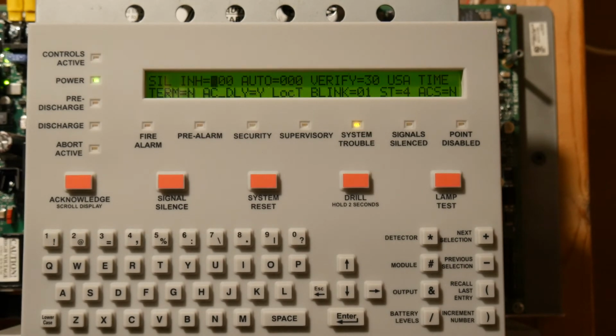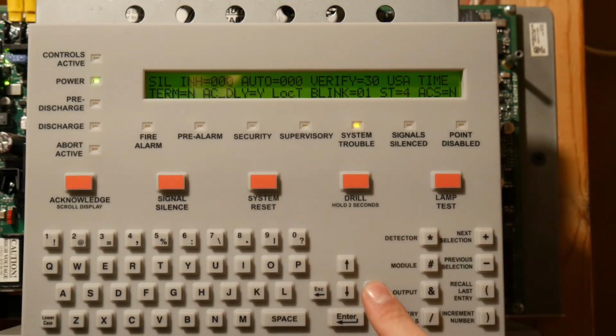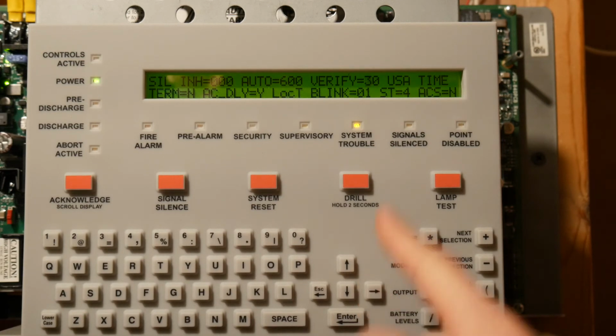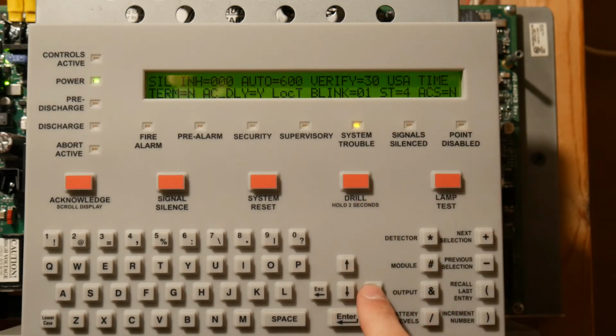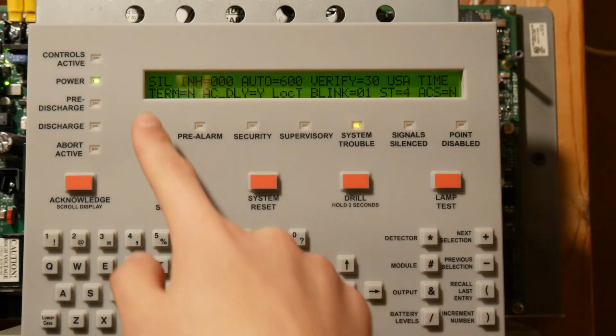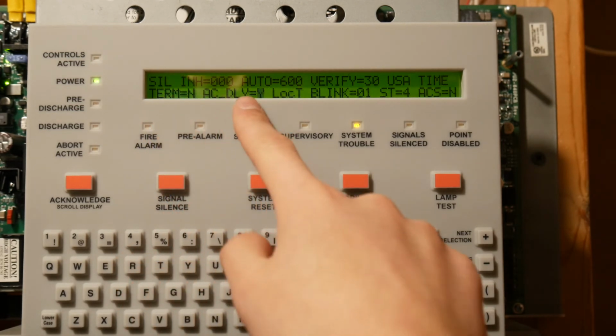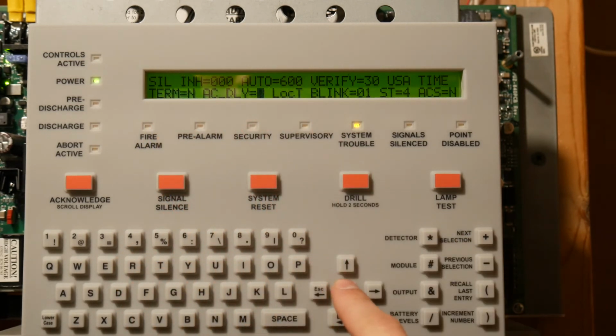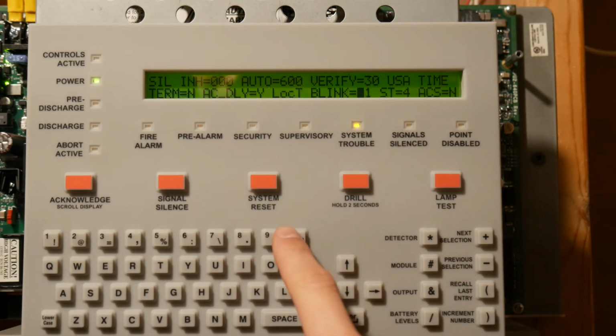Silence inhibit basically means, do you want a certain amount of time to pass before you can press signal silence? I do not want that. Auto silence, yes. I want it to automatically silence after 10 minutes. Verification is 0. We want USA time. Terminal, I don't know what that is. AC delay, yes. LED blink, yes. We want that set.